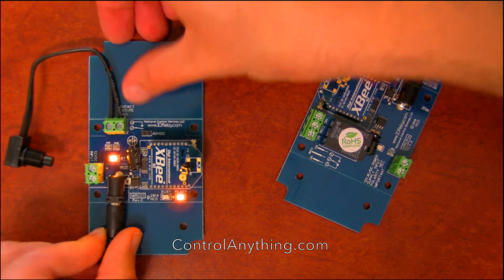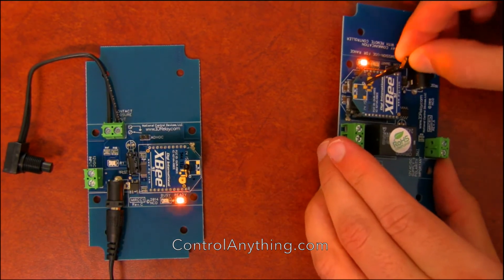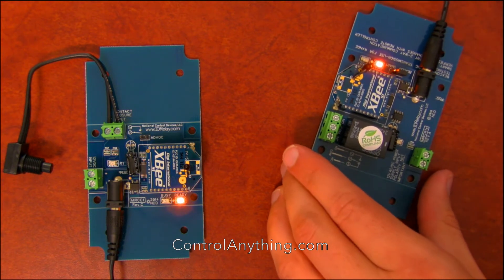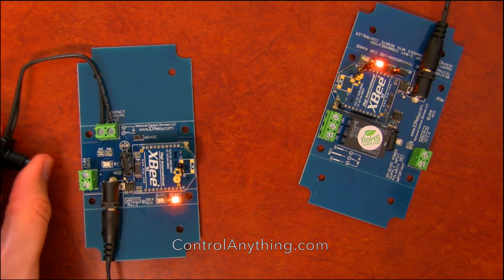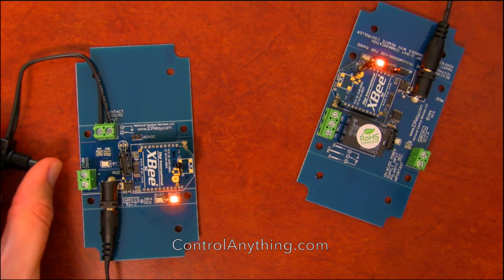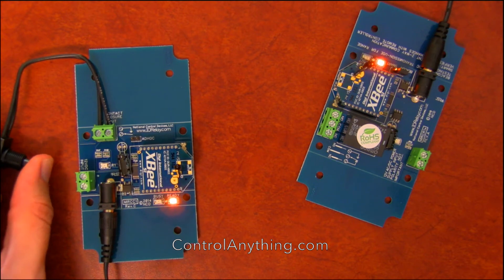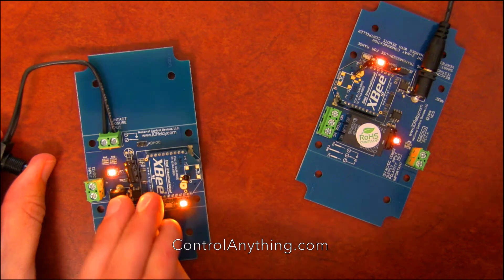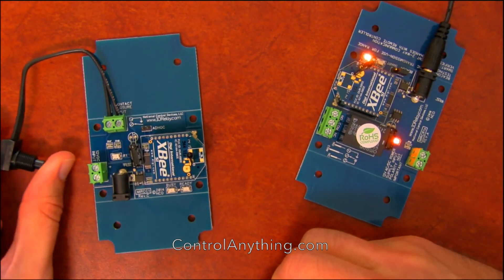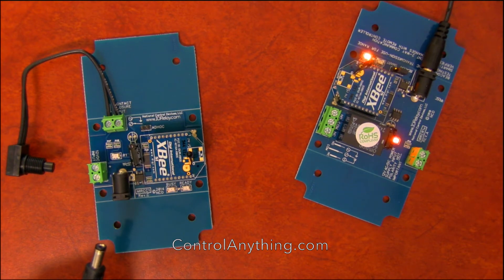Beacon mode works in a very different way. When I switch this controller over to beacon mode, the controllers begin talking very quickly with each other and refresh a lot faster. What happens is if power is lost with one of the controllers, it doesn't really matter — so if I lose power with the transmitter, communications will stop but the relay will still stay on.